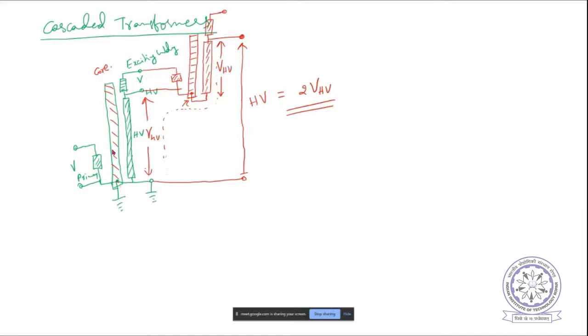So we'll have to keep it at some height or isolated. You have to create some insulating basement or insulating post for that, on which the transformer has to be placed at a particular height. You cannot keep the second transformer on the ground—please remember, only the first transformer can be on the ground. The second transformer should be floating at a high voltage potential.